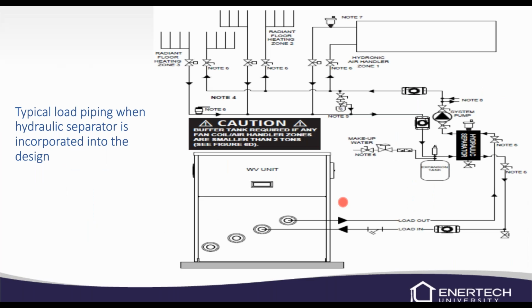This is a typical load piping. And here we're using a hydraulic separator, which is incorporated into the design. The hydraulic separator is actually just like a buffer tank. Basically, it's a lot smaller. We're not storing anything, but like a buffer tank, it decouples the zone piping from the unit piping. So it decouples the flow.